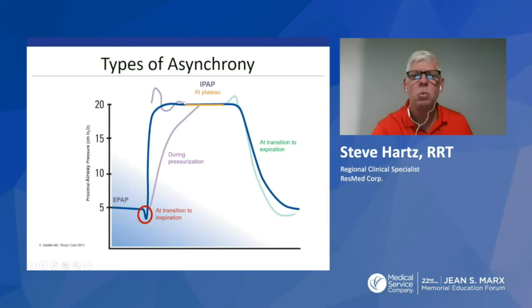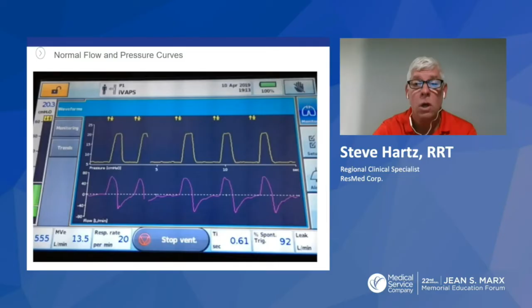Normal flow looks pretty good. This is from a ventilator, looking at a 15-second screen, and it will rescale if it needs to. Here you want to look for patient effort, triggered breaths, potentially cycled breaths, tidal volume, and respiratory rate. Now we're looking at some waveform, so more natural. We know that most of these are delivered in a square waveform, but you can soften some of them with flow measurements or changes to match the disease. How many people breathe the same way every time? None, but that's a pretty decent looking waveform here.